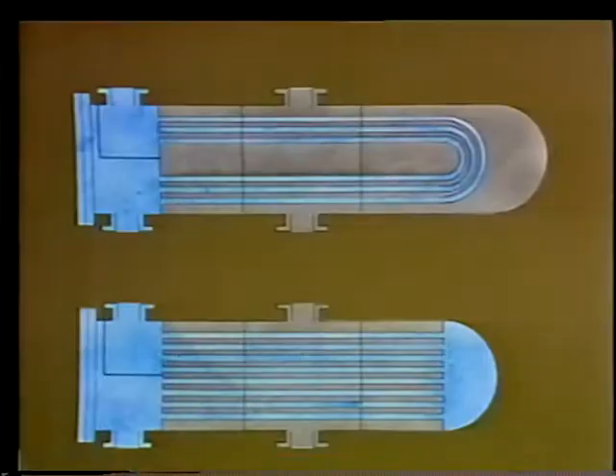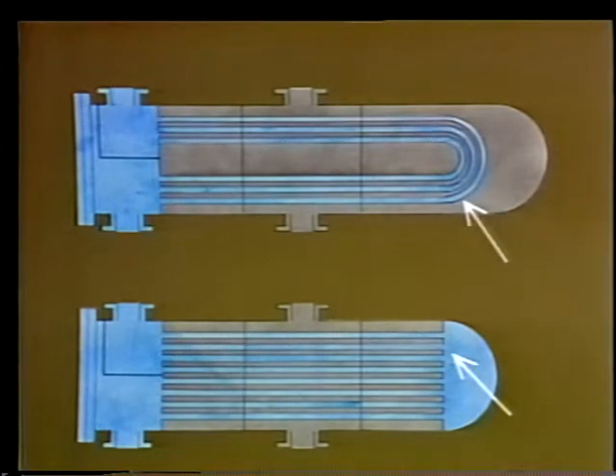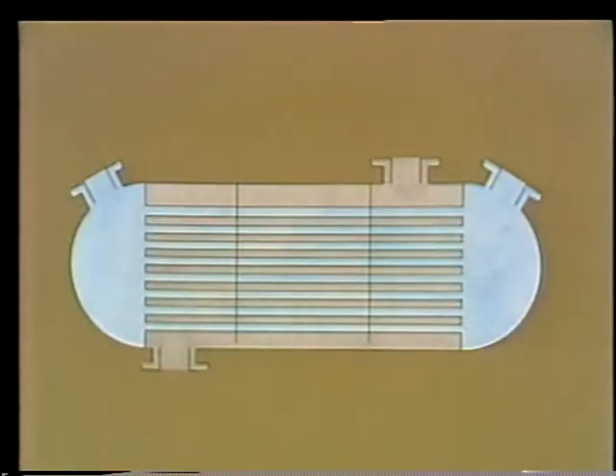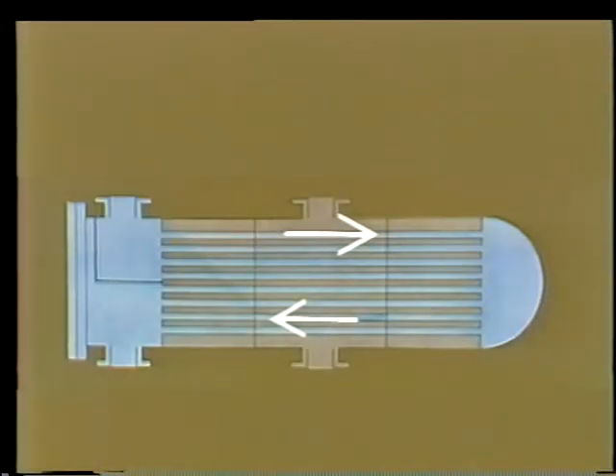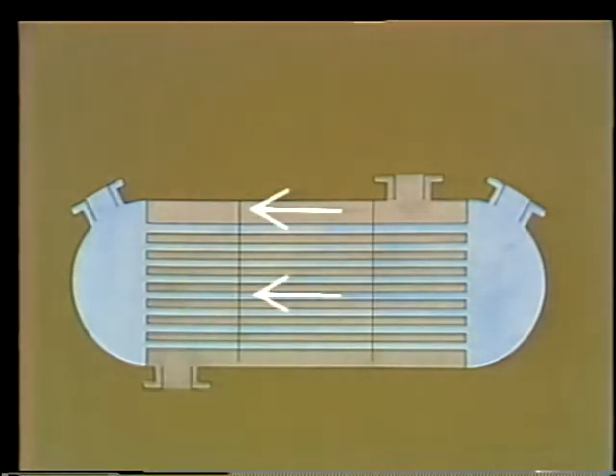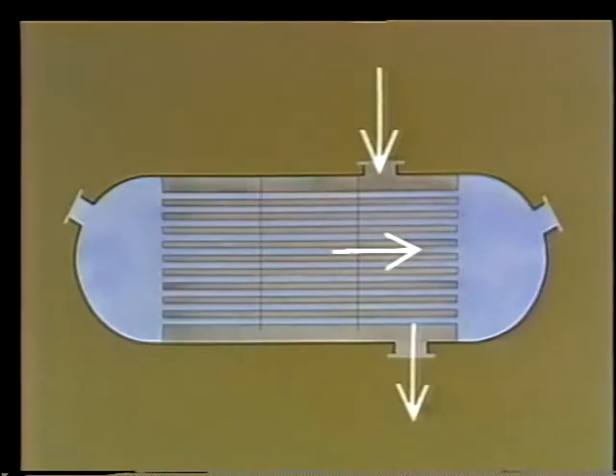Shell and tube heat exchangers come in several different arrangements. They may be either vertical or horizontal depending on space considerations. The way the tubes are arranged also differs — you may have straight tubes or U-tubes in a given unit. Flow through a shell and tube exchanger can be single or multi-pass for either or both of the fluids in the system. The two fluids can flow in the same direction called parallel flow, opposite direction called counter flow, or across one another called cross flow. The examples we'll be seeing have a number of different things flowing through them.